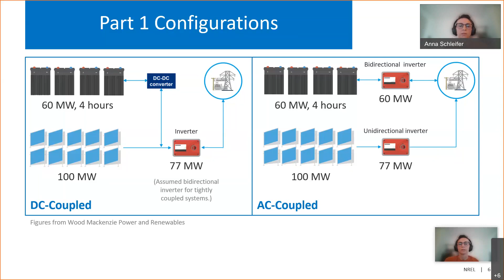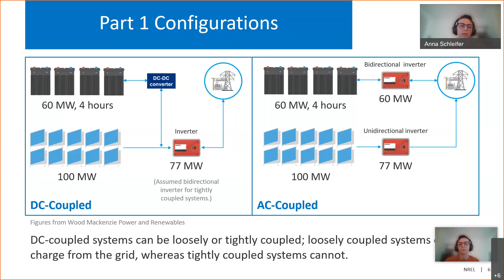The inverter was maintained at 77 megawatts here to keep the ILR at 1.3 for both systems. So again, that's the ratio of the 100 megawatt PV array to the 77 megawatt inverter. Something to note here is that the AC coupled system has a higher total output, so it has 137 megawatts of output. We didn't limit the point of interconnection capacity for the AC coupled system. And then we modeled a variation on the DC coupled system that does not allow it to charge from the grid, so that's a tightly coupled system. That's for the purpose of evaluating the effect of the investment tax credit.